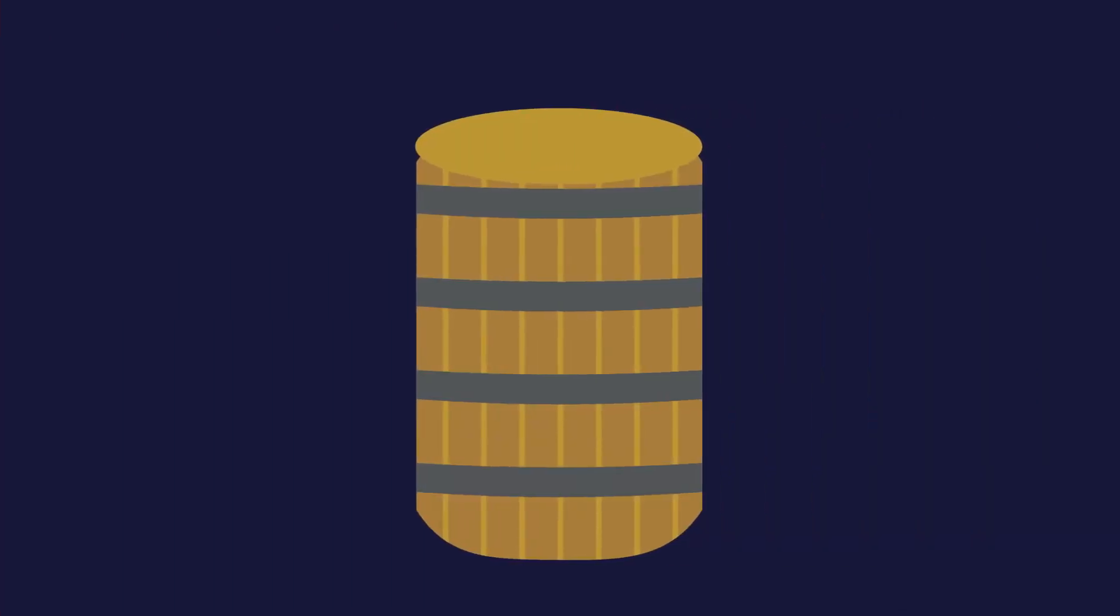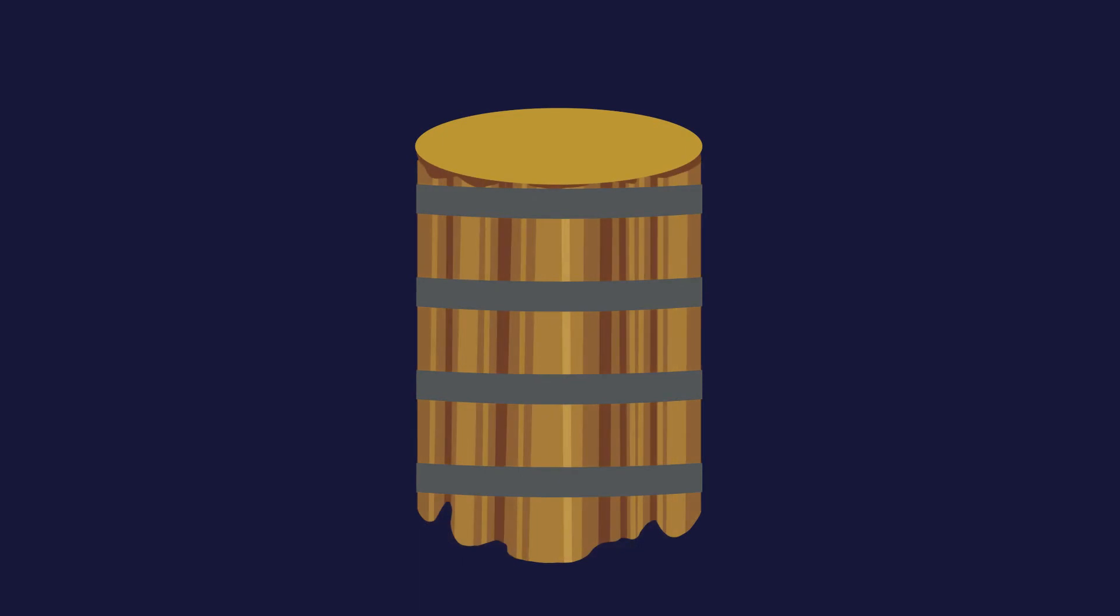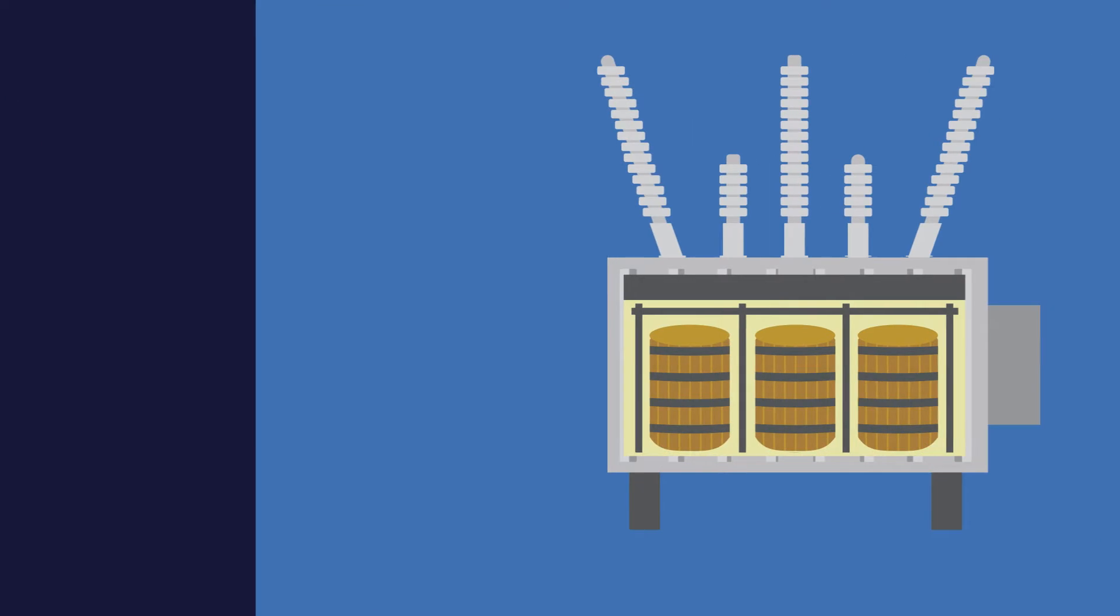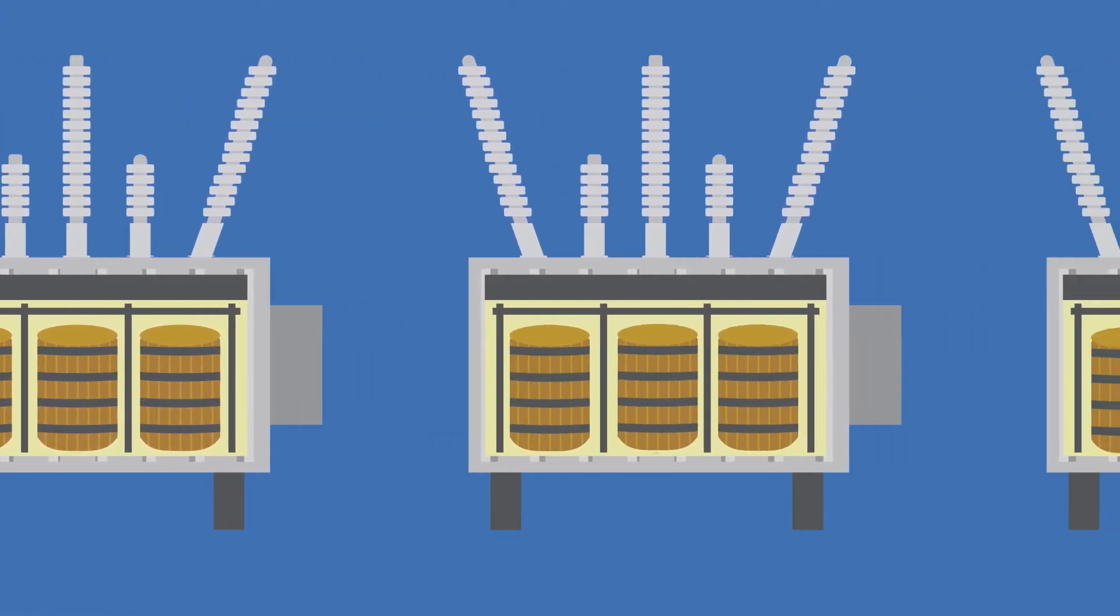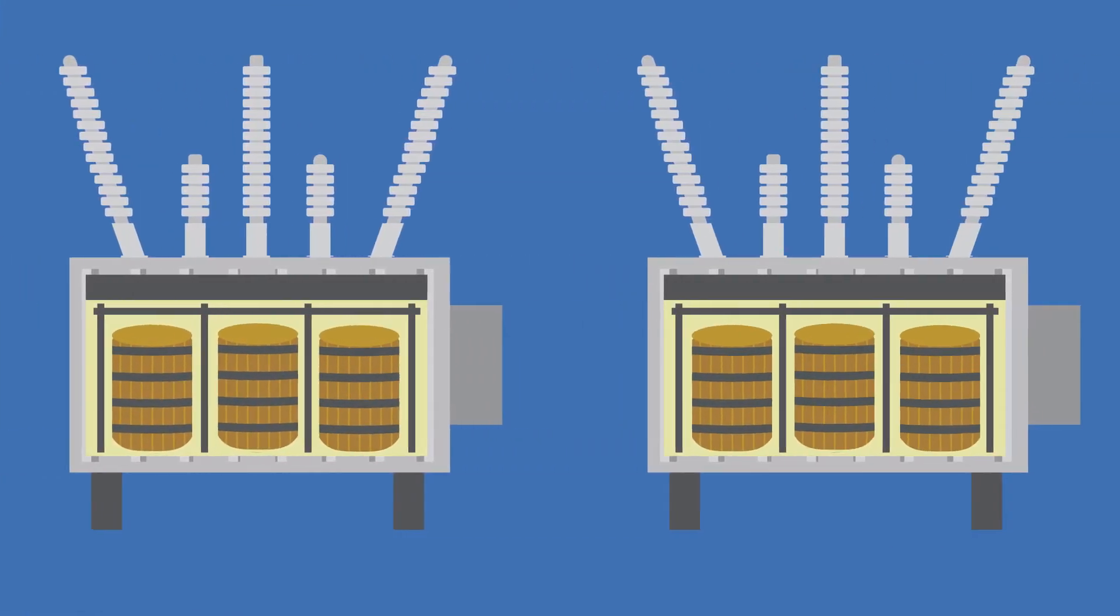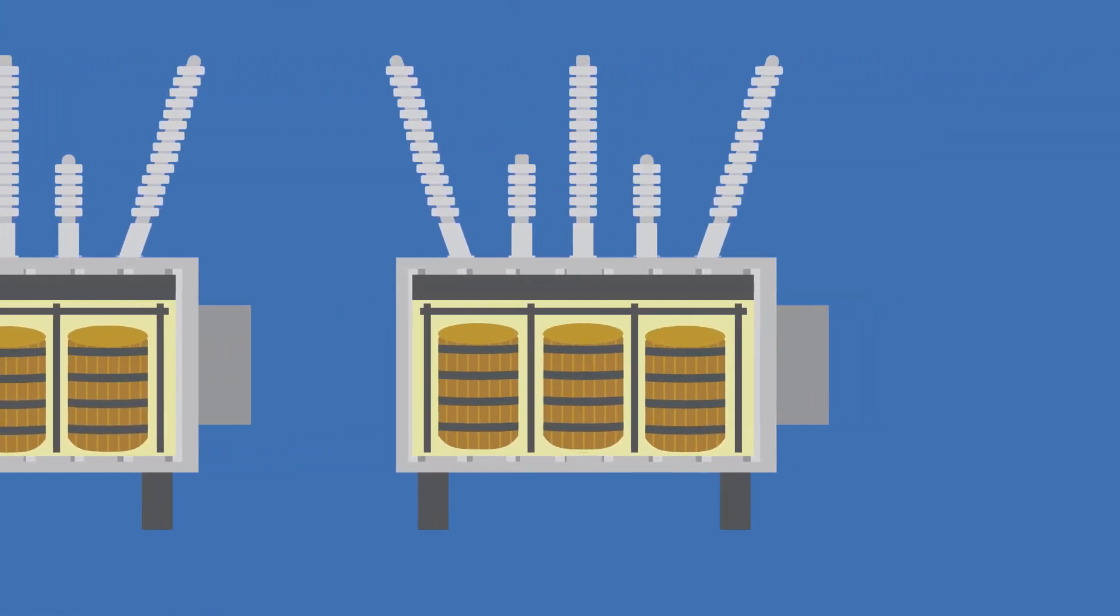This reduction of clamping force allows for more radial and axial movement of the core and coil assembly, increasing the risk of total transformer failure with each subsequent through fault.